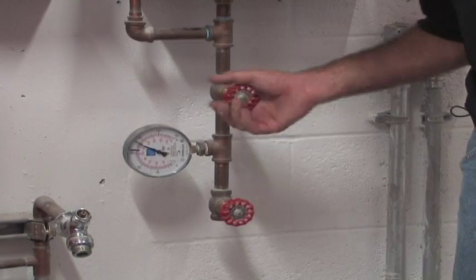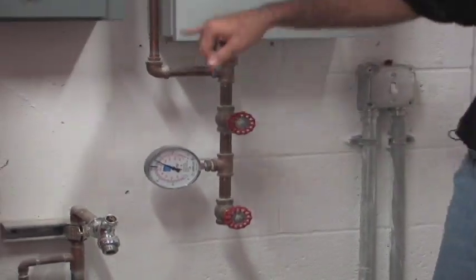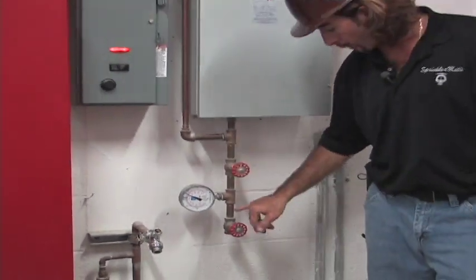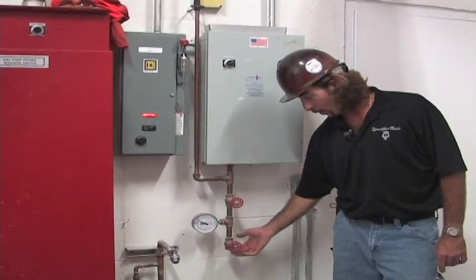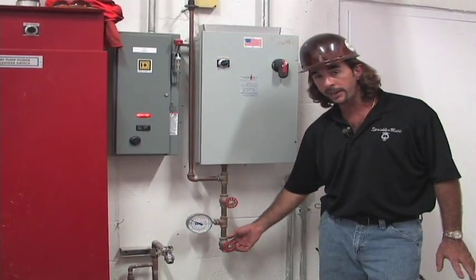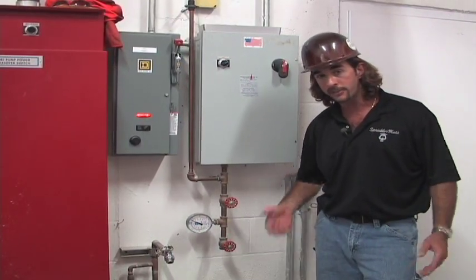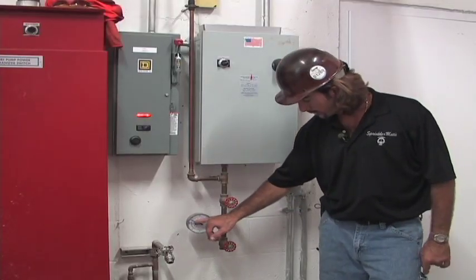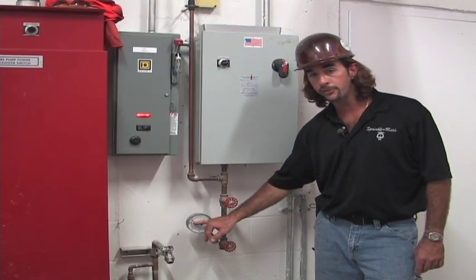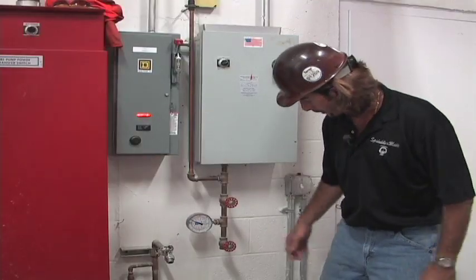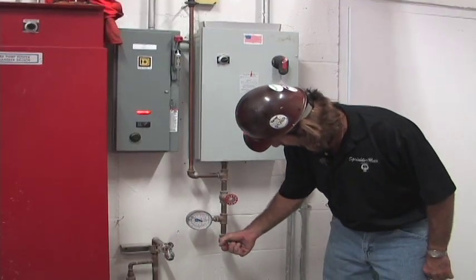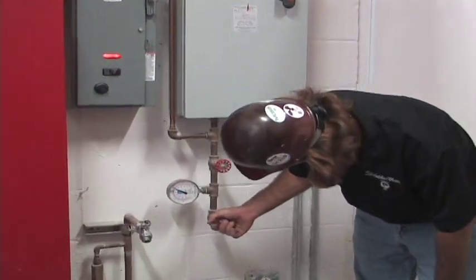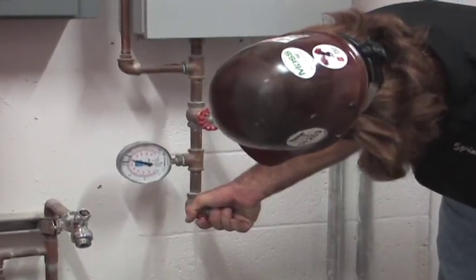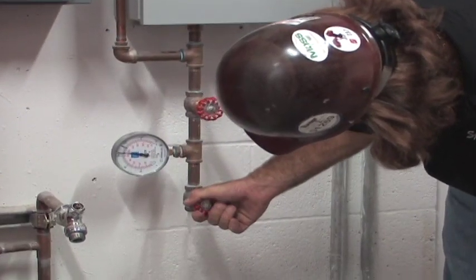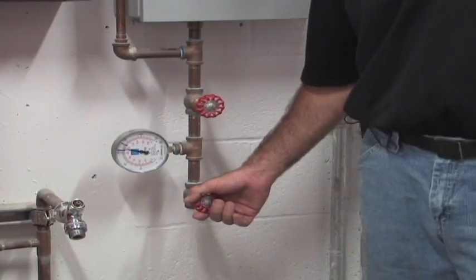So by opening up, this has two 3/32 orifice holes inside of it. So even though it's a 1/2-inch piece of pipe, the water that comes out here is going to come out spraying a little bit, but you're not going to get the full 1/2 inch. That way you can actually see what the needle actually does without the whole rush of the piping going in. So we're going to start this thing. We're going to barely bleed it open. Now the jockey pump is cycling.